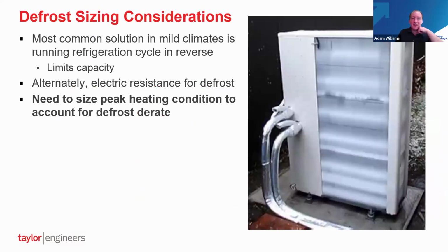So as Kyle mentioned, defrost is something you need to be concerned about. You're pumping heat from the air to the water, and as it gets colder, these units have to run in a defrost cycle. Basically, they run in reverse, and instead of being a heat pump, now they're a chiller to warm up the outside air coils so they don't freeze. Right here, the photo on the right is what happens when the defrost cycle doesn't work and you freeze up your coils and the unit doesn't work, right? So these run in a defrost cycle, and when they're running in that defrost cycle, they're not heating. So that limits the amount of capacity that they can output.